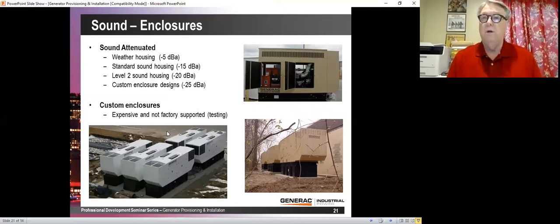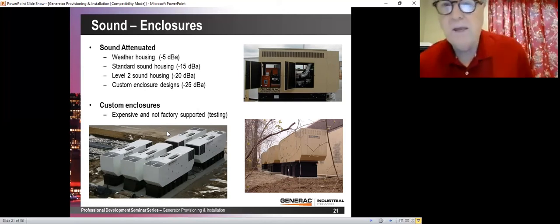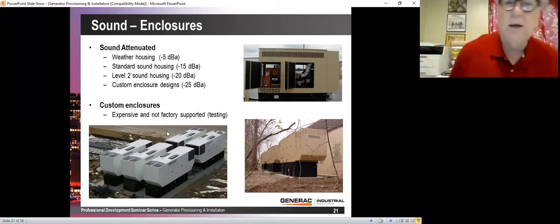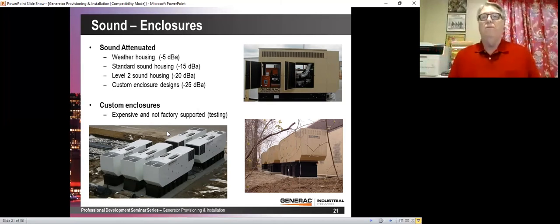If you want to know what that is at 30 feet or at 40 feet, we have a calculator that we can do that calculation for you and tell you what that sound level is further than 23 feet. Closer than 23 feet, we can do it as well, but as I said, it gets a little squirrely because you have such non-uniform distribution of the sound.